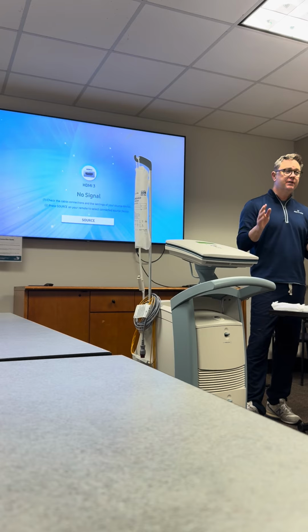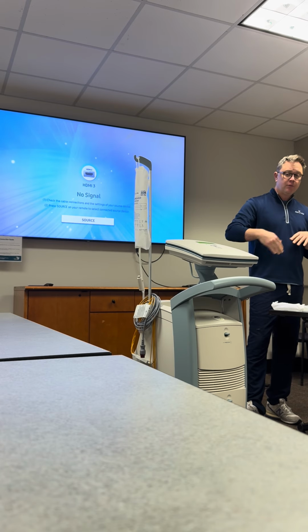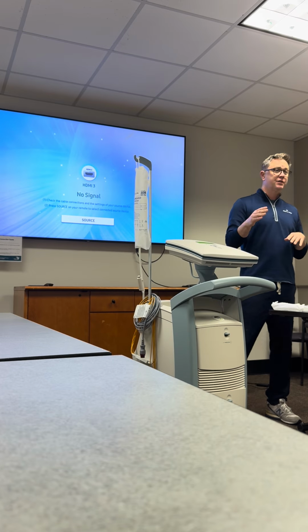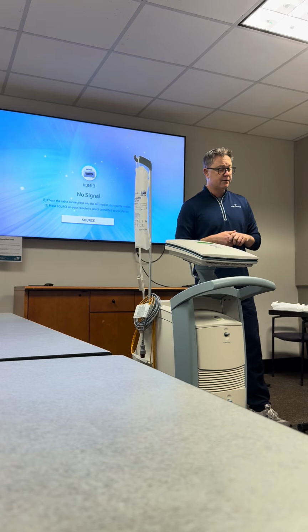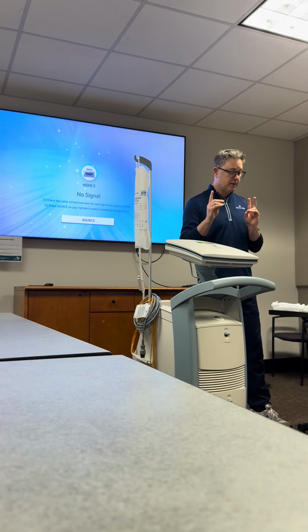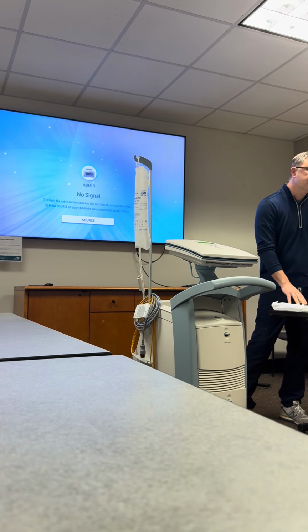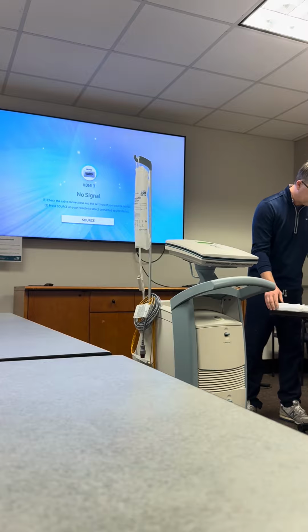If for some reason you're not able to get leads on the patient, it will go to its secondary trigger, which is the arterial pressure waveform. And there's two ways to get the arterial pressure waveform. Newest way is with our fiber optic balloons, which you guys are primarily using.